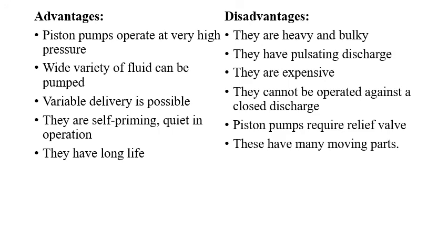Piston pumps have pulsating discharge. These pumps are expensive and cannot be operated against a closed discharge. Piston pumps require relief valves. These pumps have many moving parts.